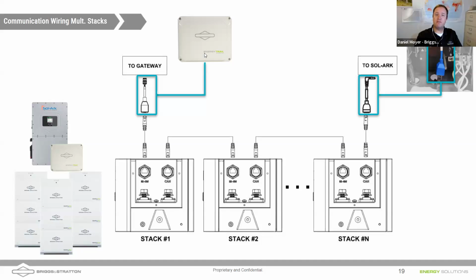Nathan, is there a certain type of Ethernet cable we should use if we're running it in the same conduit as power conductors? Well, I like using shielded twisted pairs, right? You can get unshielded Cat5 or Cat6. I guess the Cat5 versus Cat6 has to do with the capacity of the connections. You'll want to use less than 100 meters of cable. That's a standard for Cat5.